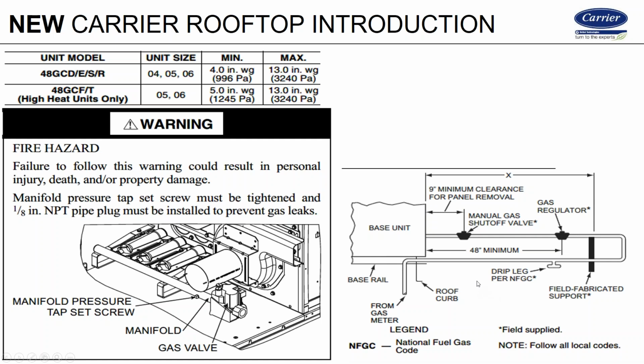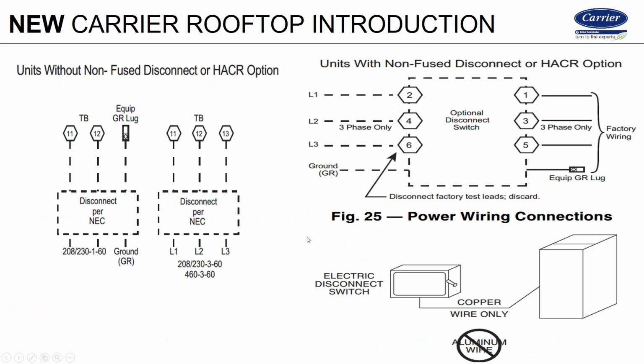So really not much more to talk about on gas piping outside of keeping all fittings at least 9 inches away from the unit. The purpose of keeping the fittings 9 inches away from the unit is so you can get the door off. If you put a coupling or a union or anything like that right here, now you can't get the door off because that door's got to be raised up and then pulled out at an angle. So that 9-inch clearance is for panel removal. So just a lot of little simple tips for installation.